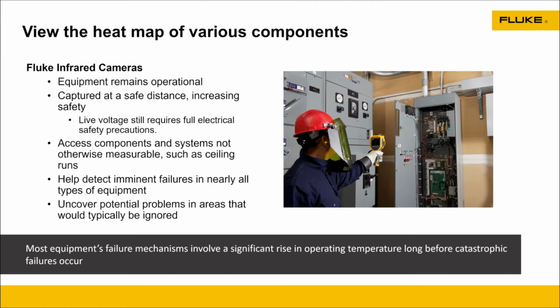But another great tool is an infrared camera. Now, again, this is allowing us to look for heat signatures, maybe components that are in there that are starting to fail. Thermal imagers are great for looking at potentially unbalanced loads, whether it's a voltage or a current unbalance. You're going to be able to see that with a thermal imager. And you're able to do that from a safe distance. Seeing those components, being able to open up that panel and look at it from a distance and start recording and doing some analysis on that.